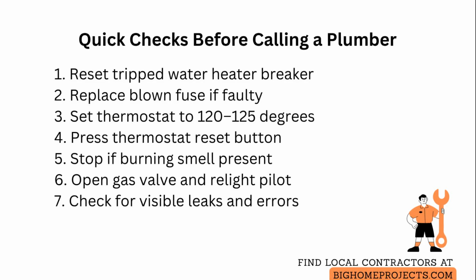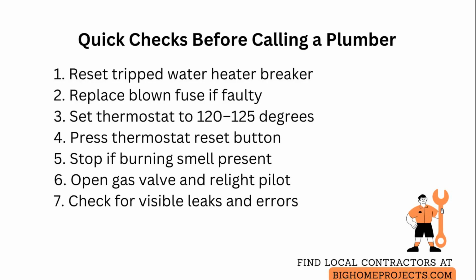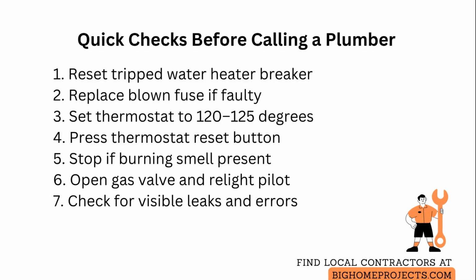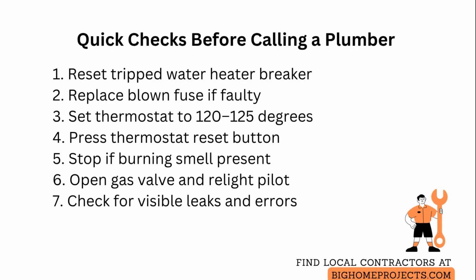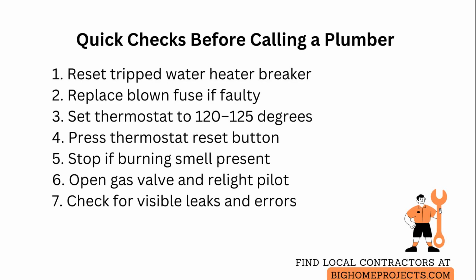For gas units, confirm the gas supply valve near the heater is in the open position, then check the pilot. If it is out, follow the manufacturer's lighting instructions with the area well ventilated and a long lighter, and wait several minutes if you recently turned off the gas so residual gas can dissipate safely.